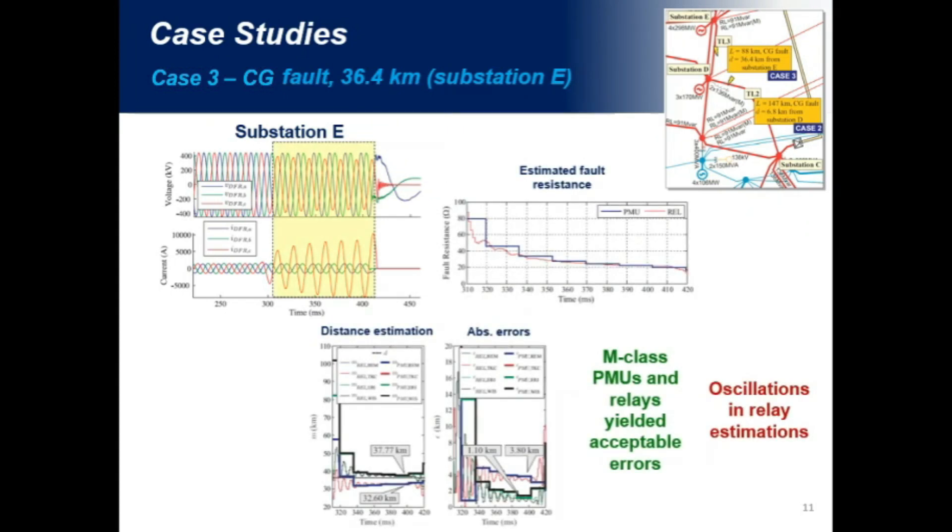Finally, analyzing the case three, we can see that this is a typical high resistance fault. We can see that the current here increases gradually, but even considering such a behavior, we could see here that estimations were very accurate. To demonstrate this case in more detail, we show here the estimated fault resistance, and we can see that it starts with a value of about 80 ohms, and it decreases until 20 ohms. But the errors did not exceed the order of 3.8 kilometers, which are acceptable for phasor-based fault location methods.